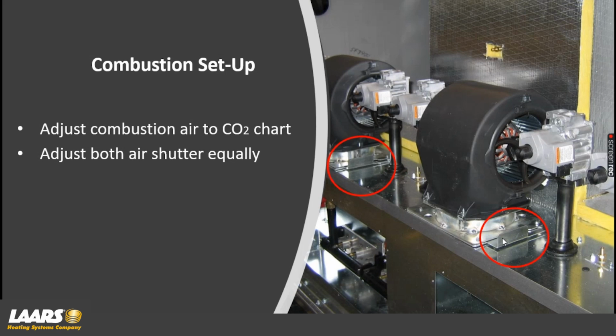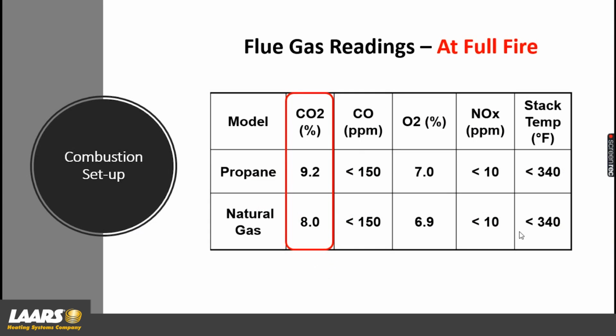And again, you want to adjust 2 blowers, any system with 2 blowers. So that's a 1250 or greater. Adjust these air shutters equally, okay? And go by our CO2 chart. Here is our flue gas reading. Again, I've got it highlighted in red. At full fire, that means all valves are on. Now you can go in and check your CO2 percentage. Natural gas in our example that we're doing in the video is 8%. Propane is 9.2. Okay.